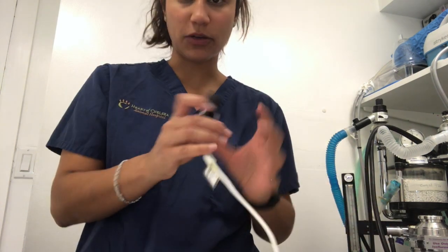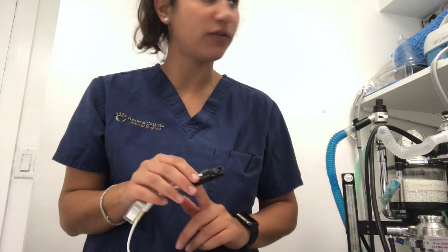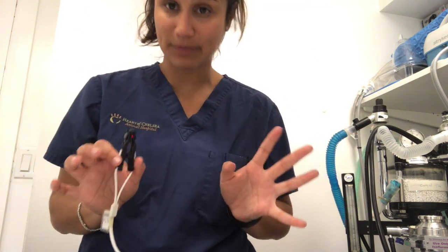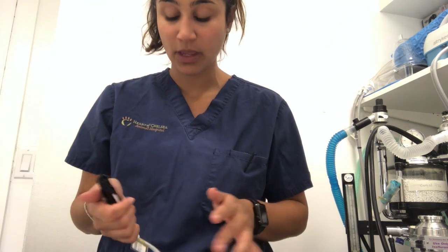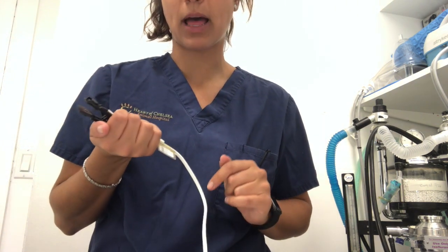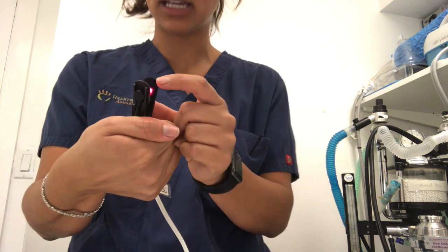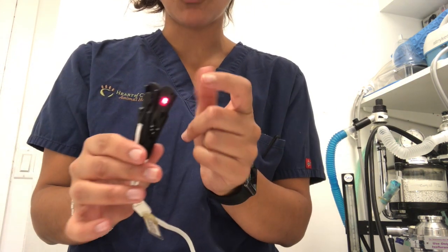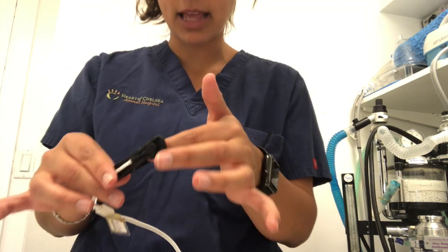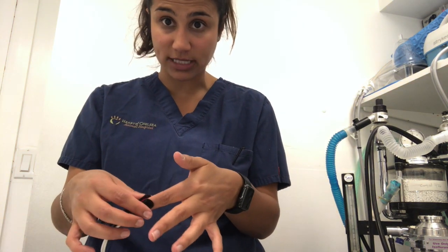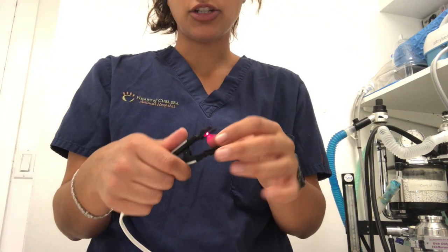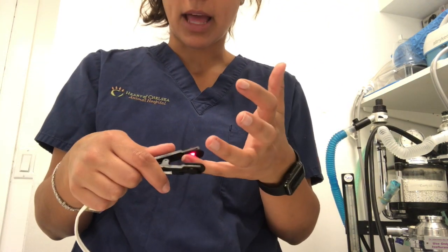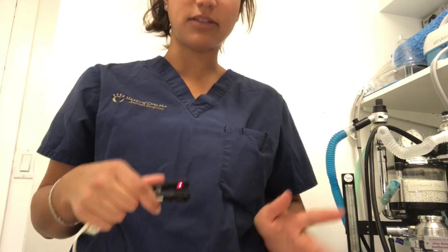Okay, so I will be talking about our pulse oximeter now. Here is the end of our pulse oximeter, and I will show you our whole machine in just a few seconds. But just to talk about it for a minute, our pulse oximeter estimates the saturation of hemoglobin. It does this from this probe. This probe has a little light on it, and it's sensitive to both the absorption of light by hemoglobin and to the blood pulsations under the skin. So this determines oxygen saturation by calculating the differences between the levels of oxygenated and deoxygenated hemoglobin.